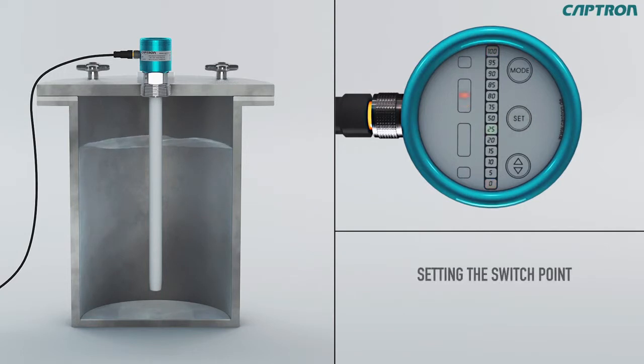The now blinking green LED shows the last value set. You can change this with up-down. When the switch output function is set on NO, the output is on high as soon as the switch point is exceeded. With the option NC, the output is on low when the switch point is exceeded. Confirm your new setting with set. The probe jumps automatically to the next step.